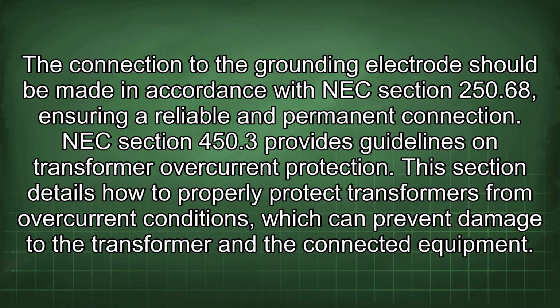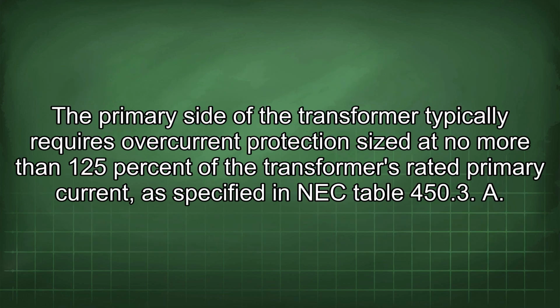NEC section 450.3 provides guidelines on transformer overcurrent protection. This section details how to properly protect transformers from overcurrent conditions, which can prevent damage to the transformer and the connected equipment. The primary side of the transformer typically requires overcurrent protection sized at no more than 125% of the transformer's rated primary current, as specified in NEC Table 450.3.